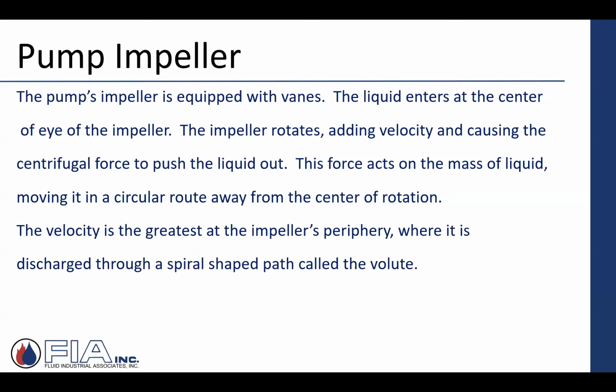So real quickly, a pump's impeller is equipped with vanes. Liquid enters the eye, the impeller rotates, adding velocity, causing the centrifugal force to push the liquid out. The force acts on the mass of the liquid, moving it in a circular route away from the center. And again, that velocity is greatest at the impeller's periphery.